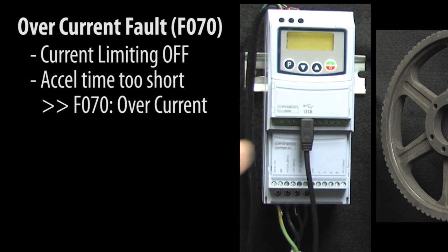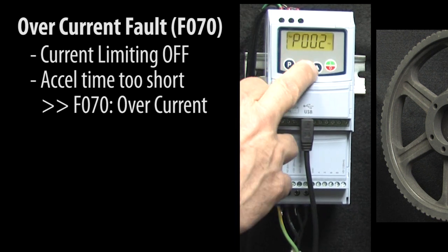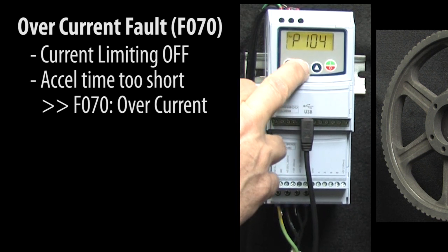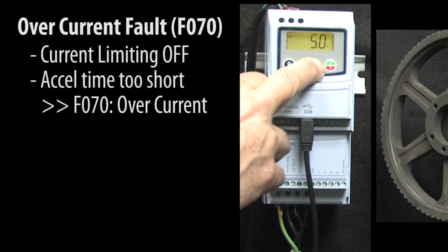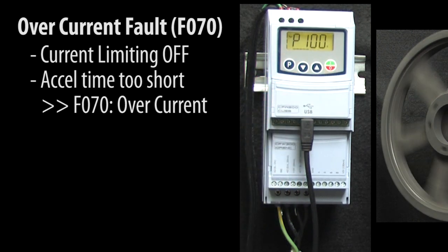So I'll hit run and we immediately get an overcurrent fault. If I clear the fault and extend the ramp time to something reasonable, say 5 seconds, then hit run, everything works great.